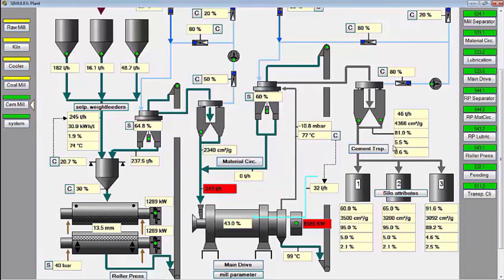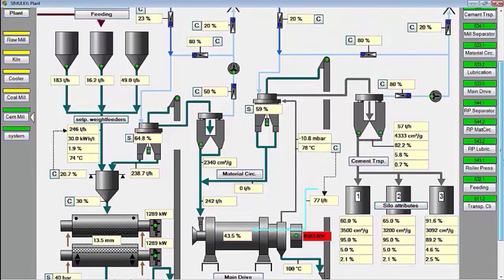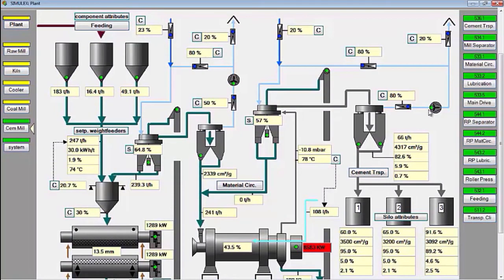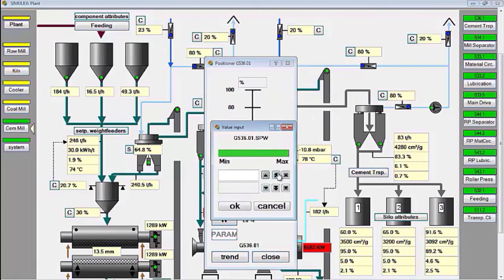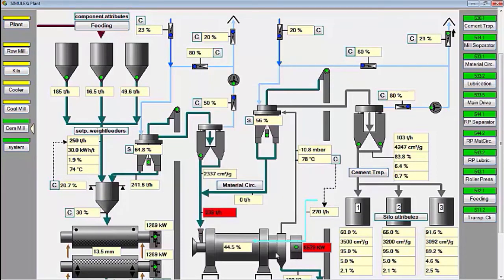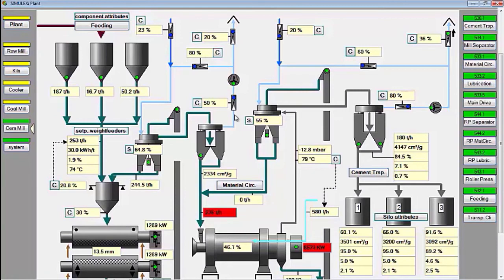The Blaine for cement products is maintained between 3600 to 3800 square centimeters per gram of cement. For the fineness of the cement product, it can be adjusted using the separator speed, the opening of the mill ID fan damper, the opening of the circulating air damper, and the fresh air damper for the separator. The mill level is maintained between 75 to 85 percent.